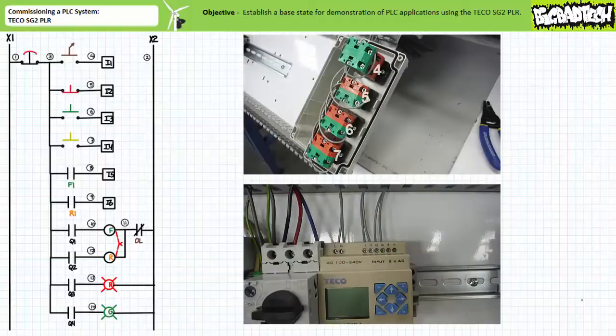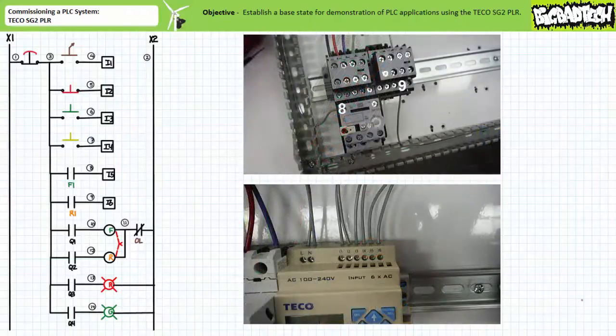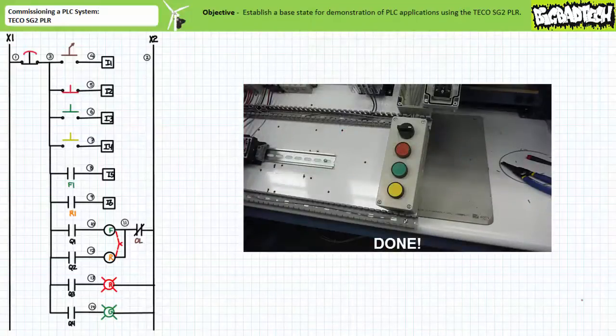Now, respectively route wires 4, 5, 6, and 7 from the first 4 field input devices to inputs I1, I2, I3, and I4 on the PLC. Similarly, respectively route wires 8 and 9 from the F1 and R1 auxiliary contacts to inputs I5 and I6 on the PLC. Theoretically, one can now button up the bottom push button enclosure containing the first 4 field input devices and never have to open it again. Let's now move on to the output.